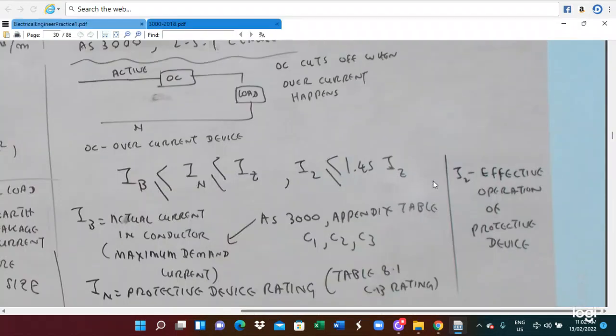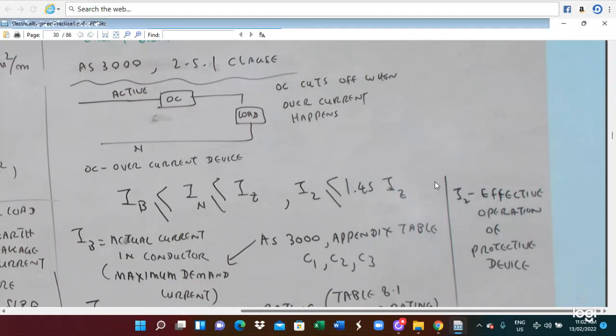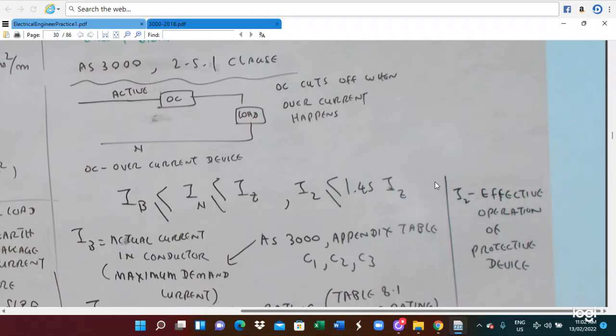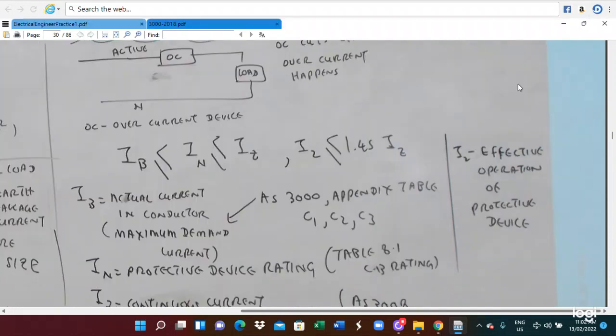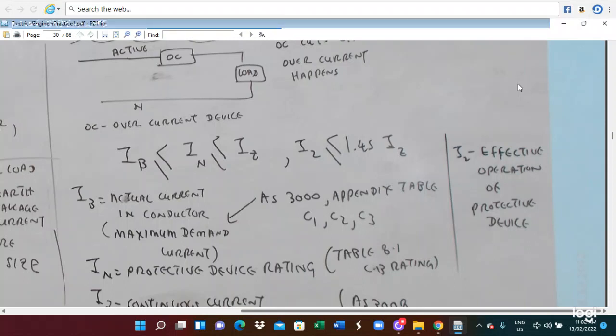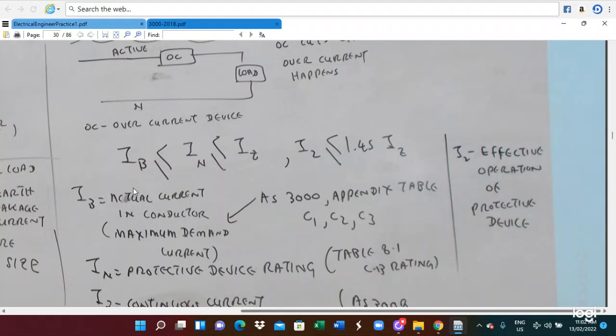Therefore, when you are selecting the appropriate circuit arrangement, the first thing is IB. IB is the actual current flowing in the conductor. This is related to the maximum demand. To calculate the maximum demand, the important thing is we have to refer to the AS3000 rule, appendix tables C1, C2, C3. C1 for the domestic installation, C2 for the industrial installation, and C3 for the energy demand method. So IB we calculate by referring to the AS3000 rule, appendix tables C1, C2, C3. This is the IB.